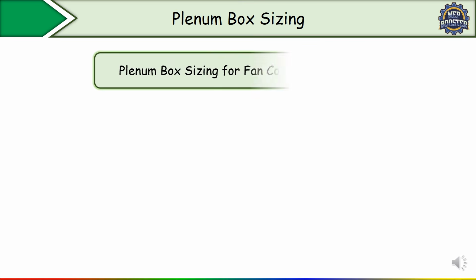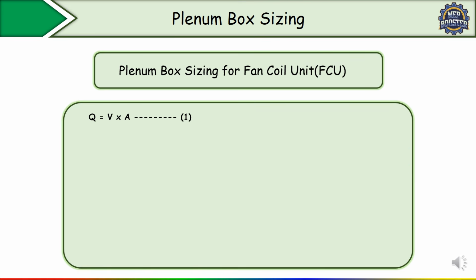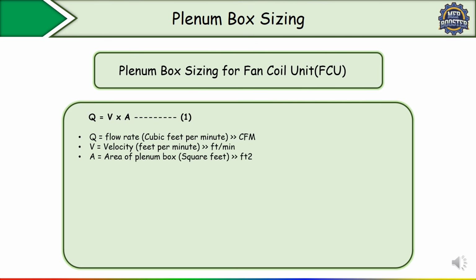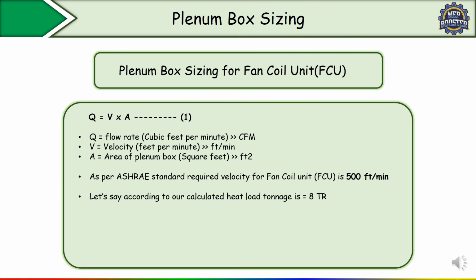Next, I will show you the plenum box sizing for a fan coil unit. It is the same procedure, only the velocity we have to maintain for sizing the plenum box for a fan coil unit as per ASHRAE is different: 500 fpm. First is the same discharge flow rate formula, where Q is the flow rate, V is the velocity and A is the area of the plenum box. Our main target, as per the ASHRAE standard, is the required velocity for the fan coil unit, 500 fpm. Let's say our calculated heat load is 8 TR. As per thumb rule, you can convert it into CFM, so we have got 3200 CFM.